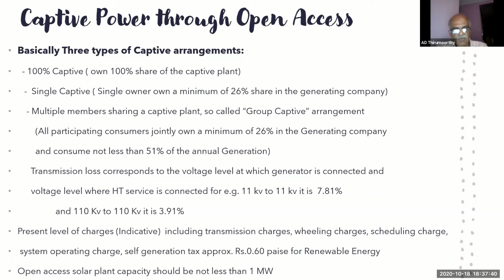For example, I have put together a very big chart for that, but I've shown only two criteria here. If he generates at 11 kV and consumes at 11 kV, the transmission loss is 7.81%. In case he generates at 110 kV level, connected to the grid at 110 kV, and the consumer is also at 110 kV level, his transmission loss is 3.91%.